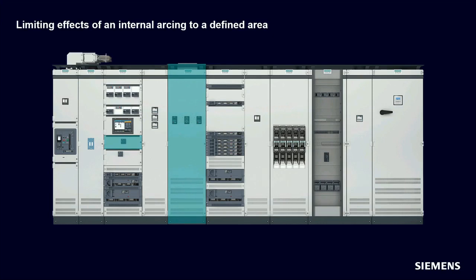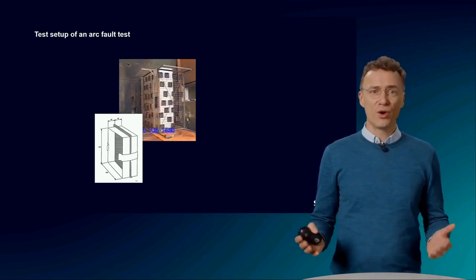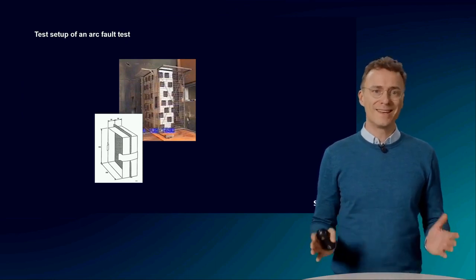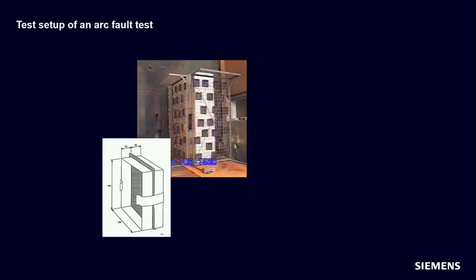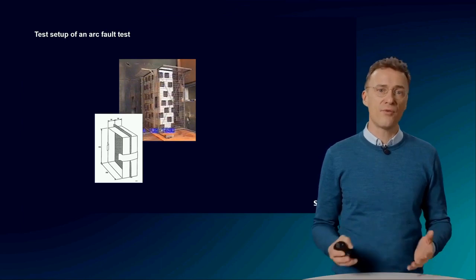After the test, it is time to evaluate the test results. There is a grid standing in front of the test specimen with small rectangles of fabric — so-called indicators — attached to simulate the clothing of a person standing approximately 30 cm in front of the system. Two different fabric qualities can be used: a lightweight cotton fabric designed to replicate unrestricted access like leisure wear, or a heavy fabric of around 150 g per square meter representing the work clothes of staff with limited access.